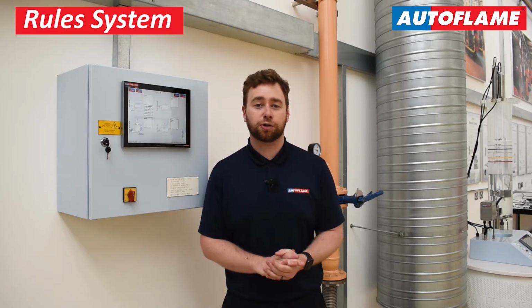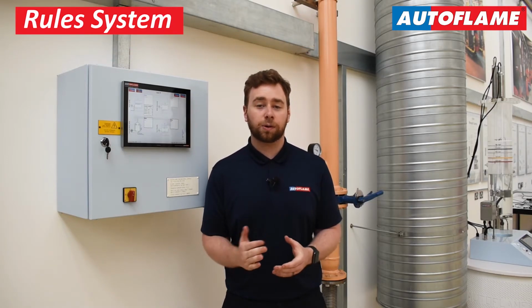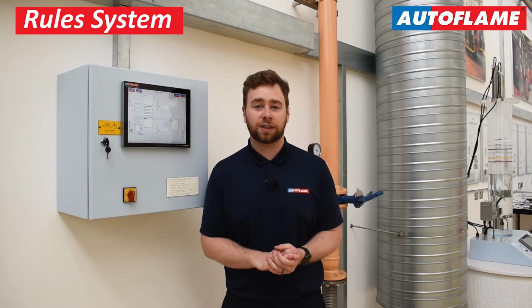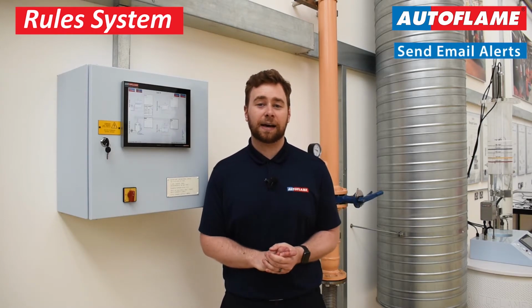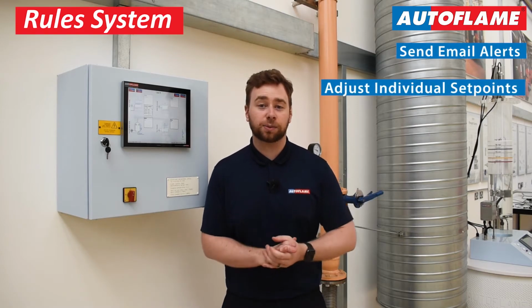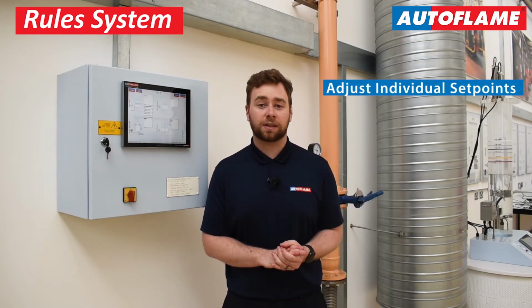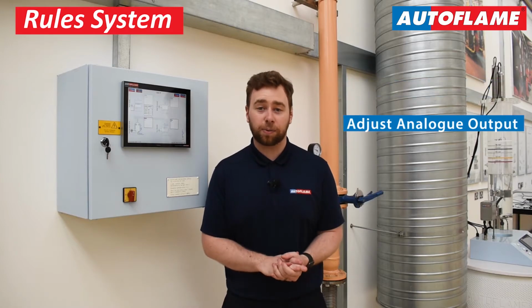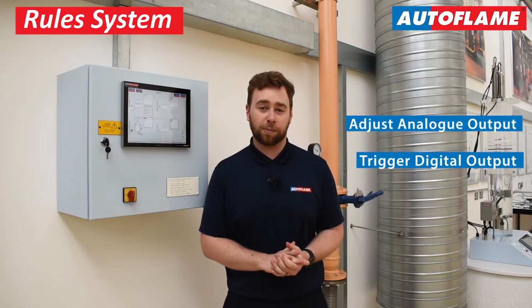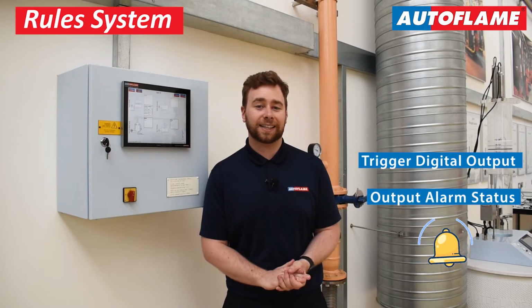So upon a triggering event, a rule can be configured to perform actions such as send an email to up to 10 email addresses, adjust individual set points, adjust an analog output, trigger a digital output, or even output an alarm status.